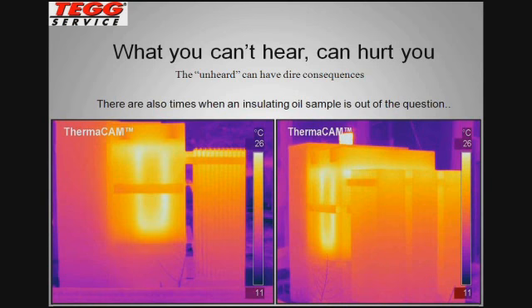a longer period of the arcing taking place to release these gases depending on the amount of oil that's within the vessel. Typically when we're dealing with liquid-filled transformers, we're talking about vessels that have a minimum of 500 to 700 gallons of oil in it. So to detect the combustible gases in there, the arcing will have had to take place for a longer period of time than we'd like to see. It's a great way to verify, particularly in the early stages, do we in fact have this occurring inside. There's combinations of gases that are very specific to arcing, as well as tracking, and as well as corona.